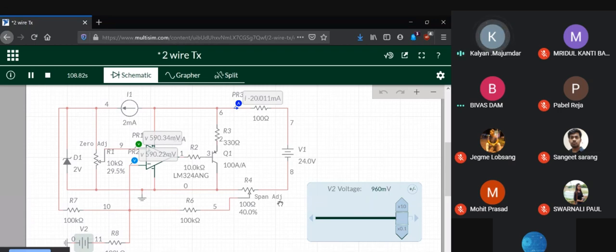Adjusting the zero and span to get the desired input range, মানে আমাদের একটা ইনপুট রেঞ্জ থাকবে যে কতর জন্য 4 আর কতর জন্য 20, সেটার জন্য জিরো স্প্যান অ্যাডজাস্ট করা to get the desired input range, সো দ্যাট যেই ভ্যালুর জন্য 4 পাওয়ার কথা তার জন্য 4 পেলাম, যেই ভ্যালু অফ ইনপুটের জন্য 20 মিলি অ্যাম্পিয়ার পাওয়ার কথা সেটার জন্য 20 মিলি অ্যাম্পিয়ার পেলাম। That is what is the calibration of the transmitter. A suitable adjustment of the zero and the span to accurately define the input measurement range. The output range is always fixed 4 to 20.